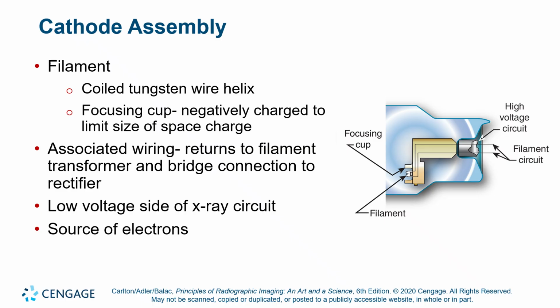So the second part of the cathode assembly is the focusing cup. The focusing cup also supplies a negative charge, but the whole point of the focusing cup, now not always does it supply a negative charge. That's one of the new re-engineerings. And I think I'm coming up to that slide. But traditionally, the focusing cup, if you supply it with a negative charge, it's bathtub shape. So the upper rim, remember, sharp radius of curvature, that's where charge seems to concentrate. So that upper rim of the bathtub, as indicated by the arrow there, is where the negative charges are going to appear to stack up, and effectively any excited electrons coming off the filament are effectively trapped in the bottom of the bathtub until they experience the pull of the high voltage that overrides the repulsive force supplied by the focusing cup.